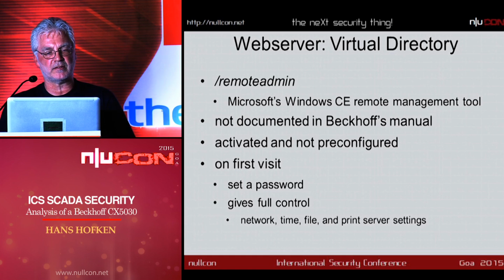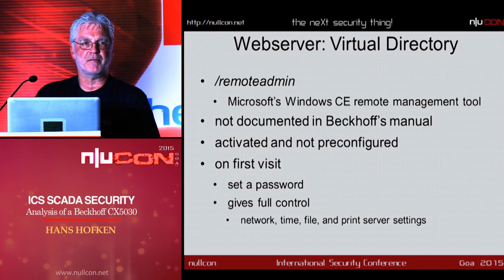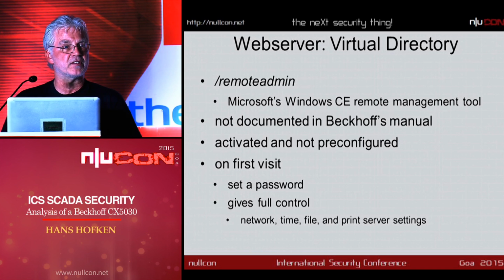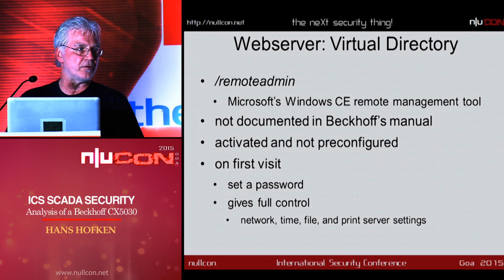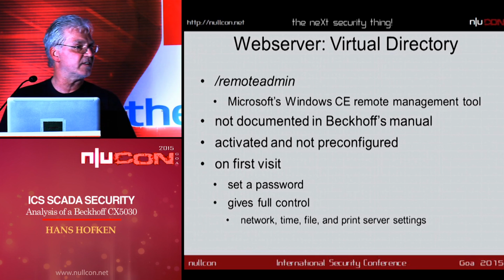What can you do with this connection? If you visit it first, you can put in a password and you have full control. Because it's not mentioned in Beckhoff's manual, mostly this feature is not disabled. If you have the connection to the PLC, you can configure network, time, file, print server settings, and so on.